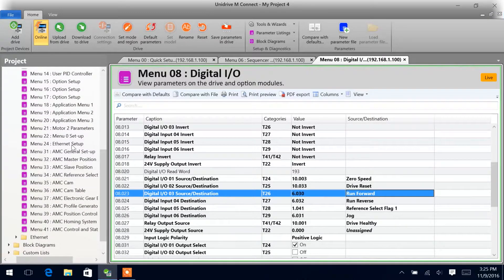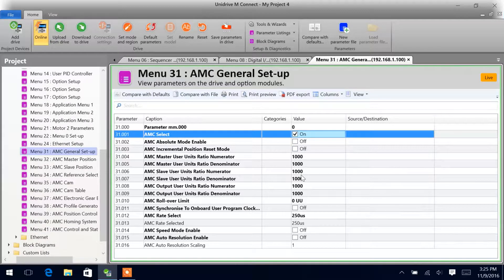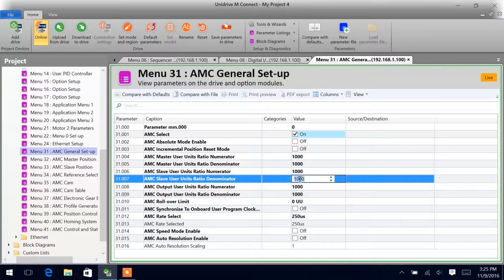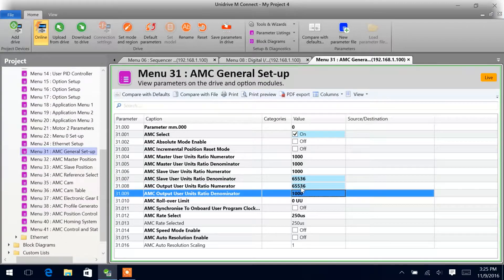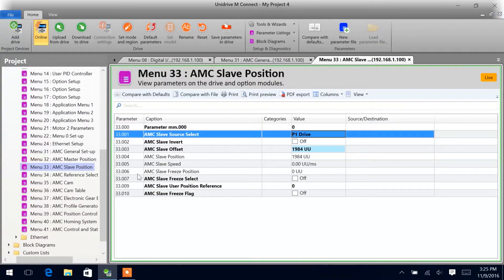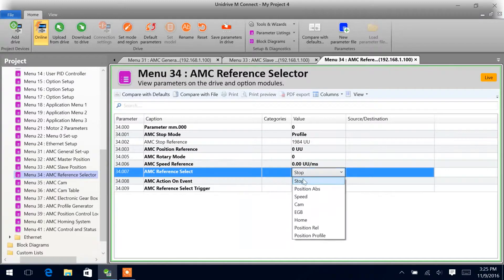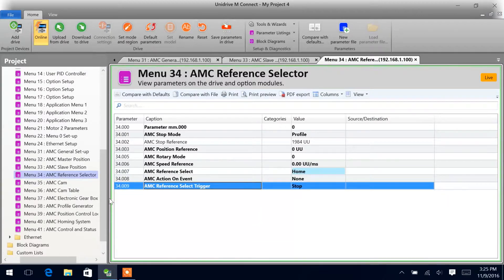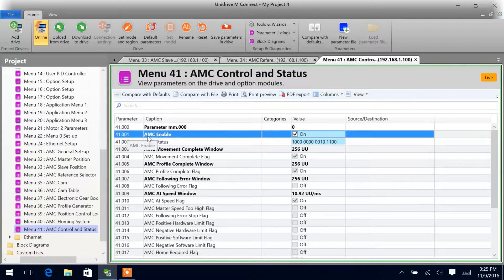Coming down now to our AMC parameters, we'll first go to menu 31 and we'll cut AMC select on. Then we'll come in here to our user units and we'll make this 65536 and change this one to 65536 as well. We want to make sure slave is on P1 of the drive. We can go ahead and change our AMC reference select to home, and we'll come over here to menu 41 and make sure AMC enable — parameter 41.01 — is on.